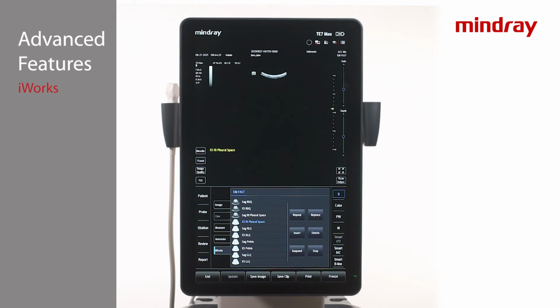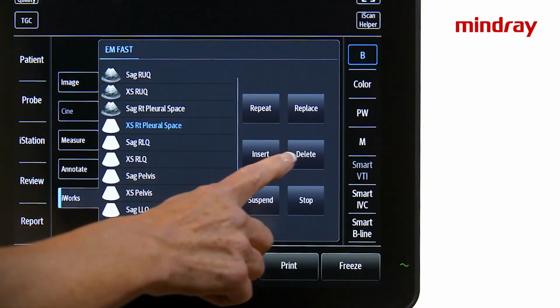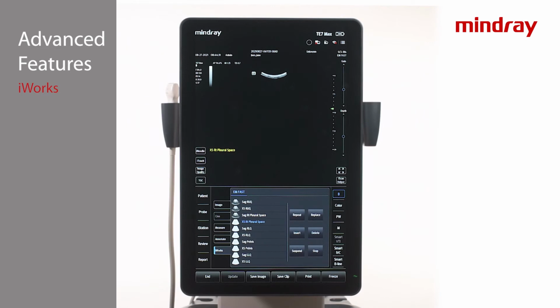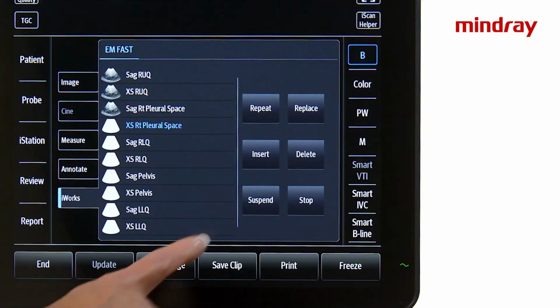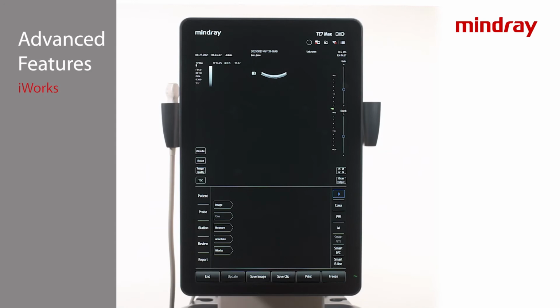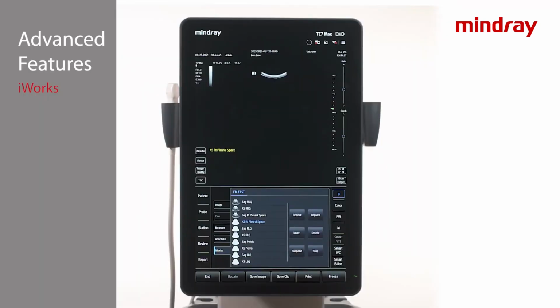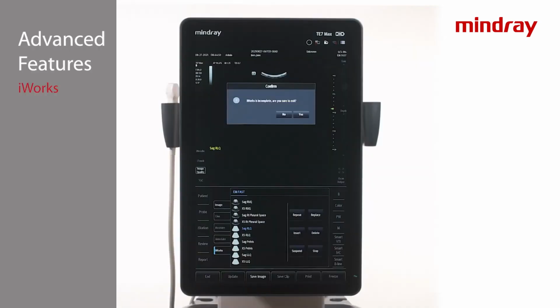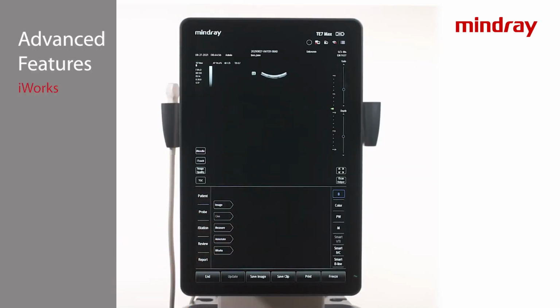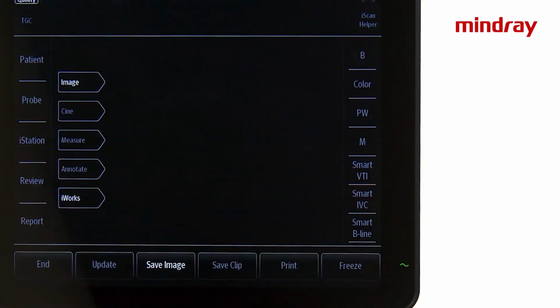iWorks is designed to offer flexibility while scanning. To the right of the views, there are tabs available to repeat, replace, insert, and delete a view. There is also the option to pause the iWorks protocol if needed and resume later. To pause, tap the Suspend tab. To resume, tap the iWorks tab again and the protocol will pick up where you left off. Continue until complete. The Stop tab ends the protocol but does not end the exam. Continue to scan the patient outside of the protocol if necessary. When ready, tap End to close the study.